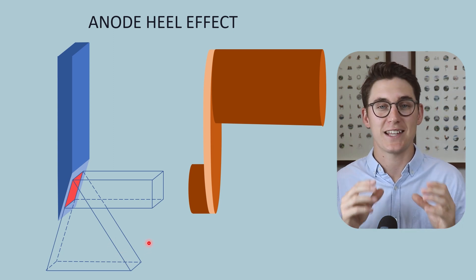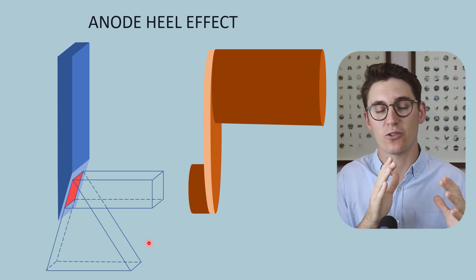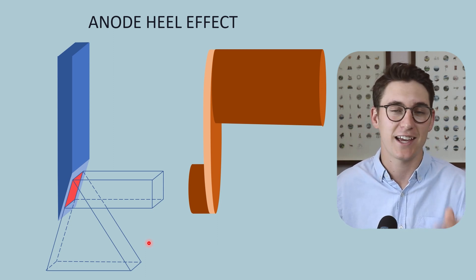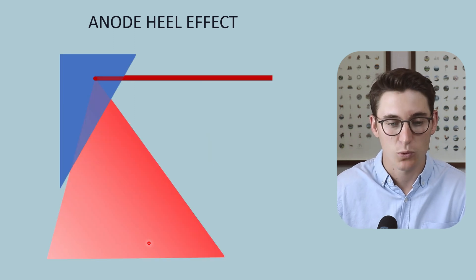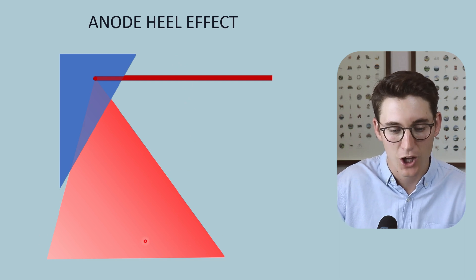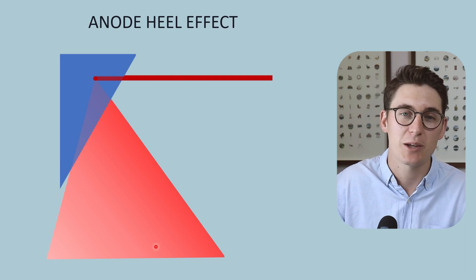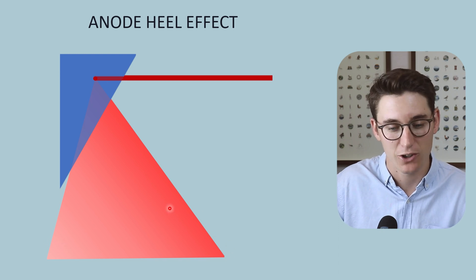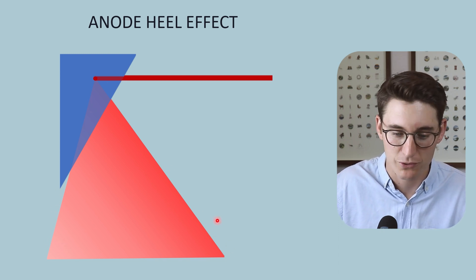Now today we're going to look at the anode heel effect and I don't want you to get confused with that variation in effective focal spot size and the anode heel effect. So what exactly is the anode heel effect? Well the anode heel effect describes the variation or the difference in x-ray beam intensity between our anode side and our cathode side of our x-ray beam or of our field.